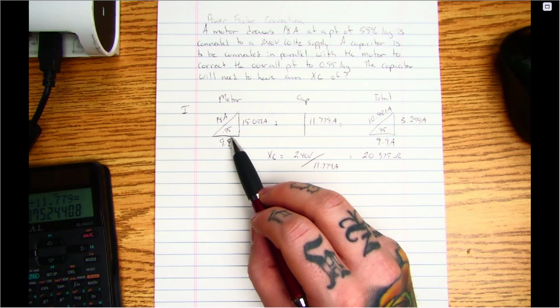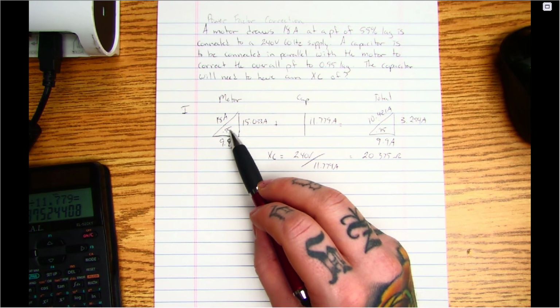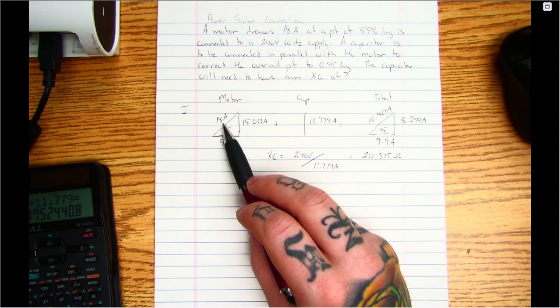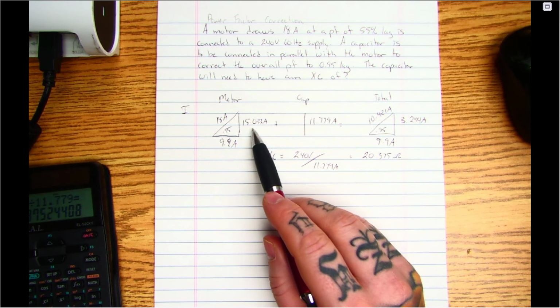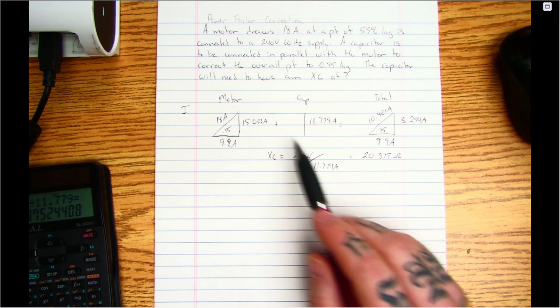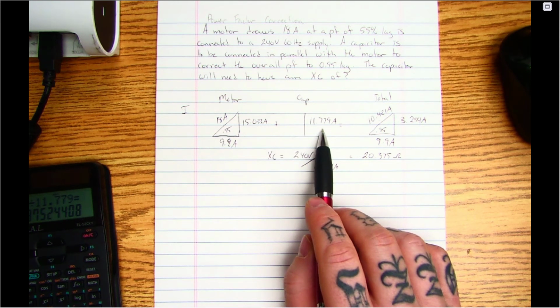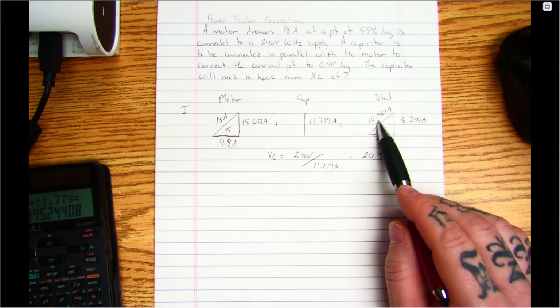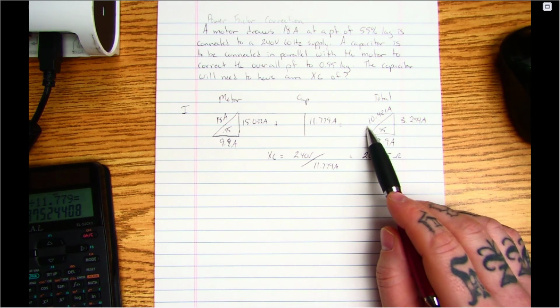We're not changing the power factor of the motor. Okay, we can never change the power factor of the motor unless we would rewind it. It runs at that power factor and it draws that current. What we're doing to reduce this line current is we're dealing with the VARs. Again, the VARs are the part that for a magnetic field to be created, power that we don't necessarily want, but we have to deal with. So we're going to feed these VARs from the capacitor rather than pulling it from the source, and that allows us to drop this current here. Okay, so that's the whole point of power factor correction, is to reduce this line current.